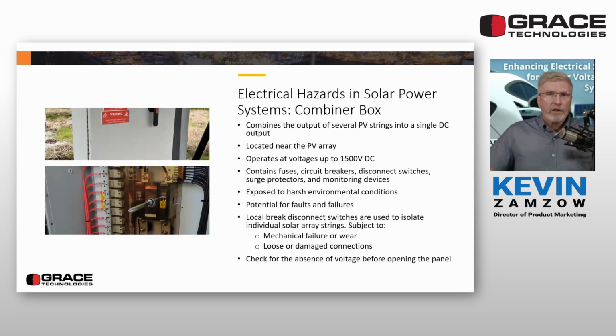The combiner box, typically located near the photovoltaic array, is a device that combines the output of several PV strings into a single DC output. It can operate at voltages up to 1,500 volts DC and contains the fuses, circuit breakers, disconnect switches, surge protectors, and monitoring devices. The combiner box is exposed to harsh environmental conditions, increasing the potential for faults or failures. In particular, the local break disconnect switch may not fully open and isolate the solar array strings due to mechanical failure or wear or loose or damaged connections. The ability to quickly verify the absence of voltage before opening the panel for service significantly reduces the risk of electrical injury.